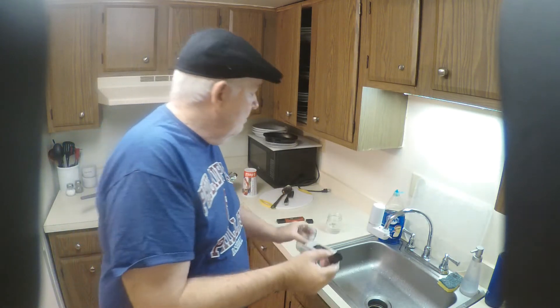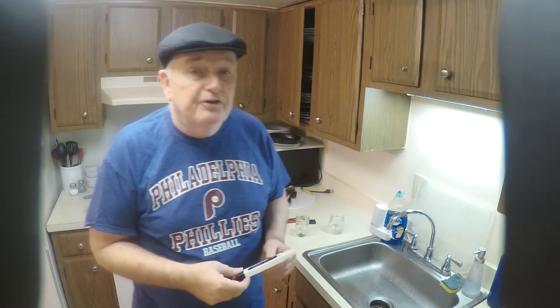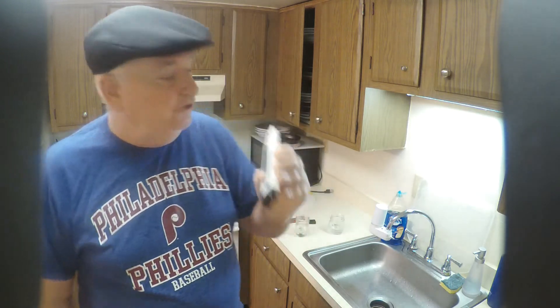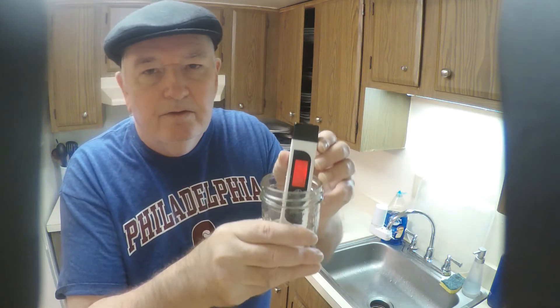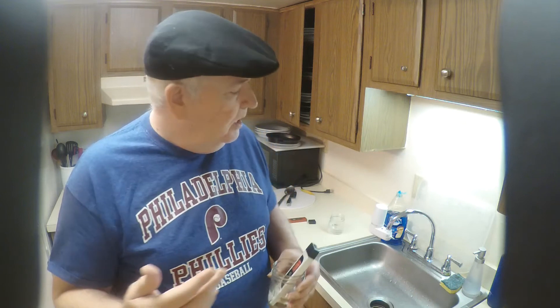We know it's coming from around the filter area and there are no new solids involved. My meter also has a thermometer on it, so I took a temperature reading and it's somewhere in the vicinity of 58 degrees. That's telling me the water is cold — coming in colder than normal. We're at the end of January, and it only happens on the bypass.